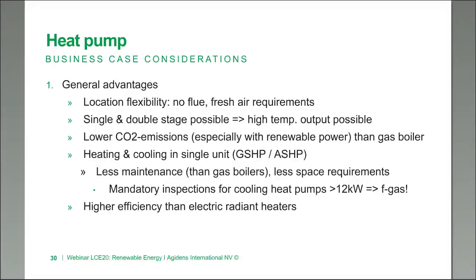Also, if you have higher heat output requirements than what the heat pump can provide, it is perfectly possible to add a double stage application to heat the medium to a much higher temperature. In many cases the use of heat pumps leads to lower CO2 emissions, especially if you're using renewable power such as solar panels or wind power for powering the compressor. You also have the advantage that in many cases you can provide both heating and cooling in a single unit, for both ground source and air source heat pumps — meaning that instead of having two different installations you consolidate into one.